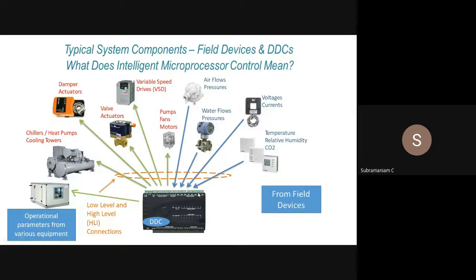Now, how the controller works. You will see some arrows going inside to the controller, some arrows going out from the controller. Going inside is the blue color. So I have the controller, and all these field devices give information to the controller as inputs. We'll see later. Based on the logic which is there, it will give output to all these devices on how to work, in what condition, in what position, what should be the position of my actuator, and things like that, to achieve that set point. Correct? So that is the job of the DDC controller.